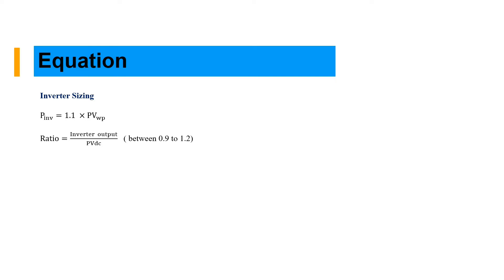Now for inverter sizing, we can use PV inverter equals 1.1 times the PV power peak. The inverter ratio should be between 0.9 to 1.2 to avoid too much losses.